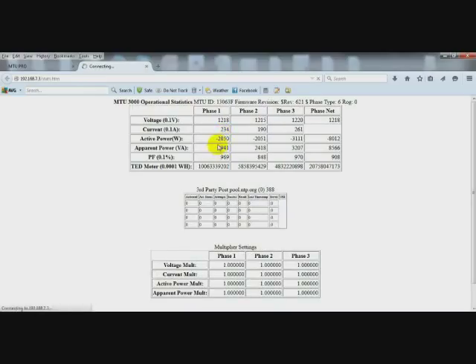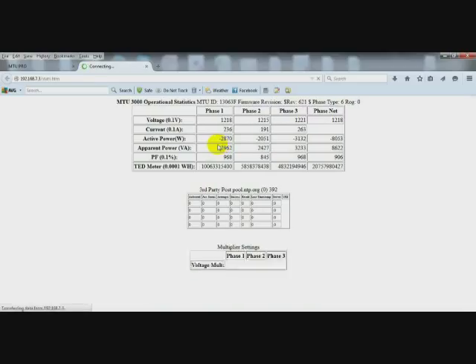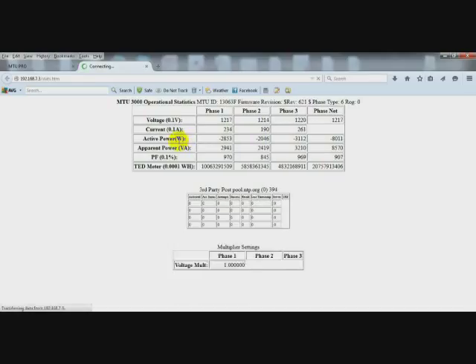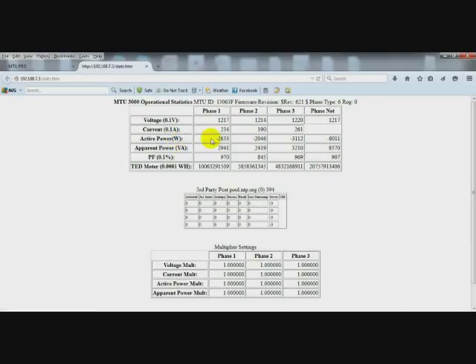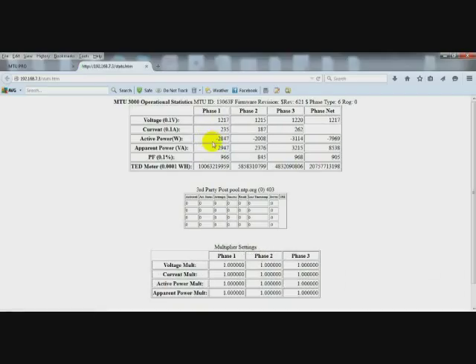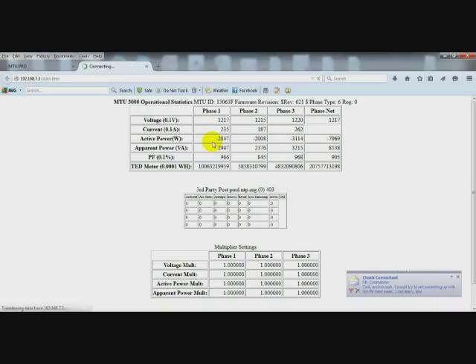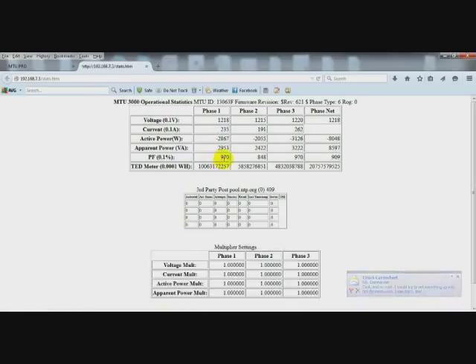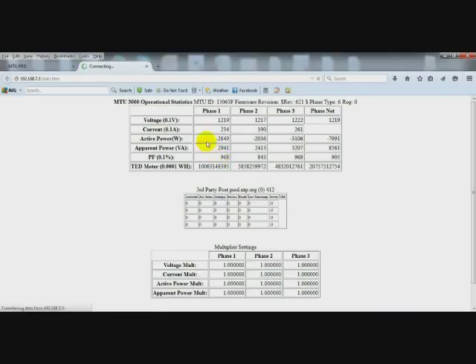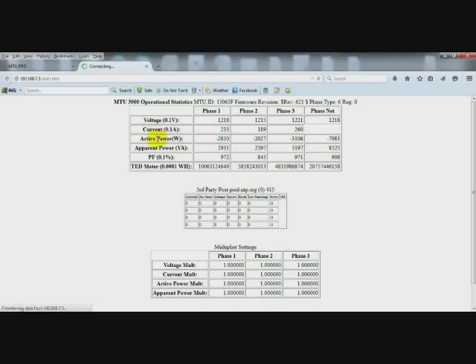And what's of most importance to us right now is we want to verify that we have a positive number for active power for each phase. Assuming you don't have generation going on in this panel, which we don't, the active power should always be positive. We also are checking that we have a reasonable number for the power factor. There's a decimal place not shown here. So while 97% power factor would be reasonable, the active power number is negative.